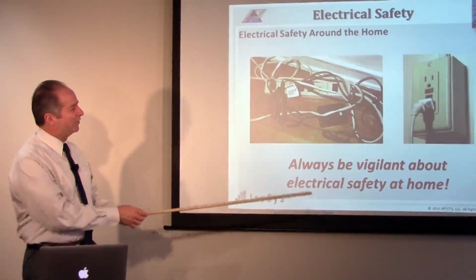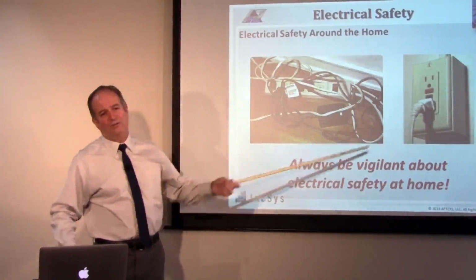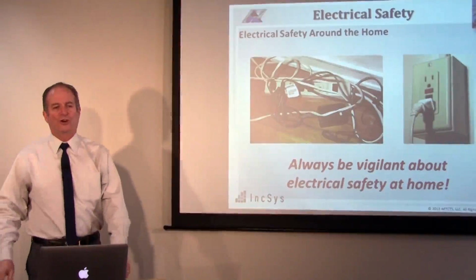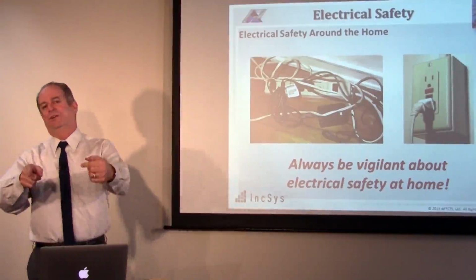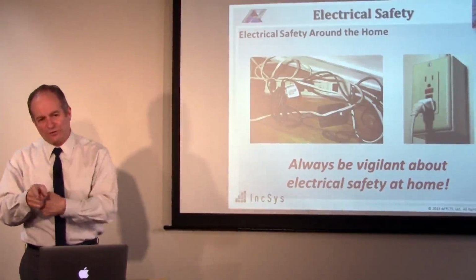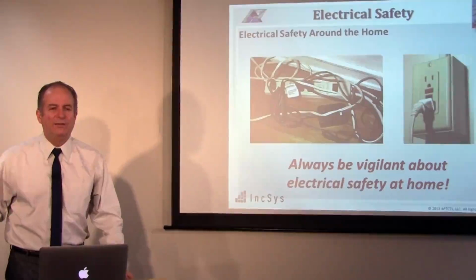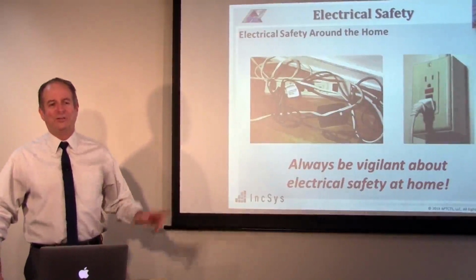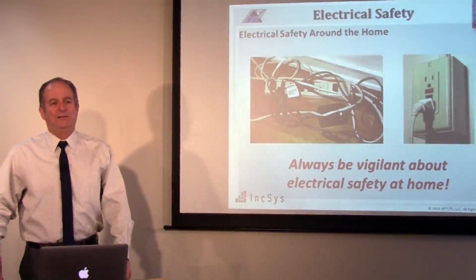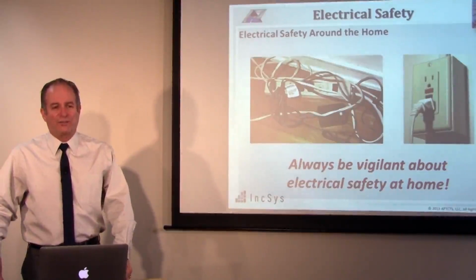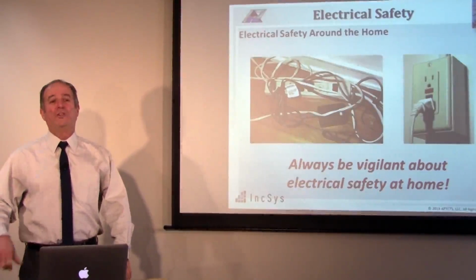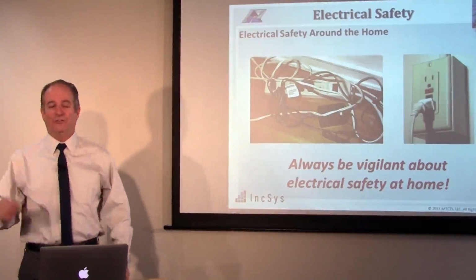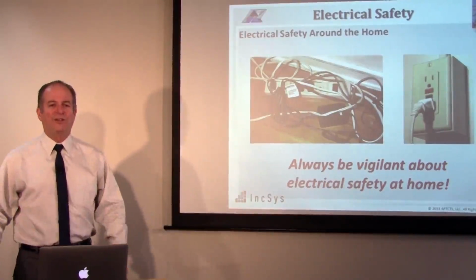Now, these ground fault circuit interrupters are designed to trip at a differential current of 5 milliamps, which means the current going out on the hot wire must equal the current coming back on the neutral wire within 5 milliamps, so that you don't have a differential condition. That little relay, if you will, assumes that if the differential is greater than 5 milliamps, that extra current is going through a human body, going through an alternate ground path, and it's not coming back on the neutral, so that breaker trips. So it's all about safety.